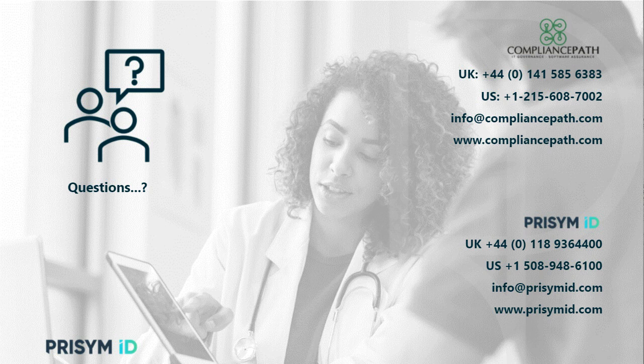Yeah, thanks, Andrew. So I think there's a couple of different areas that are certainly evolving at the moment. To take it back 3 or 4 years, the FDA in the US came out and said that they were looking seriously at aligning the quality system regulation, which is the current regulation for medical devices, 21 CFR Part 820, and starting to look at harmonizing that with ISO 13485. I think with COVID and everything that's come with that, that's probably slowed that initiative down a little bit.